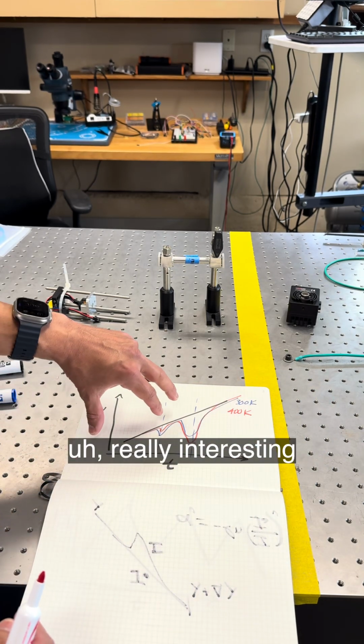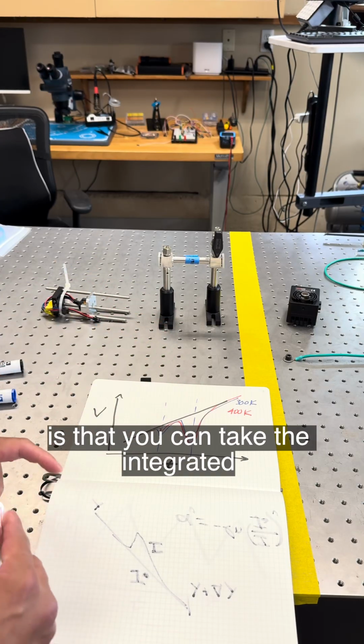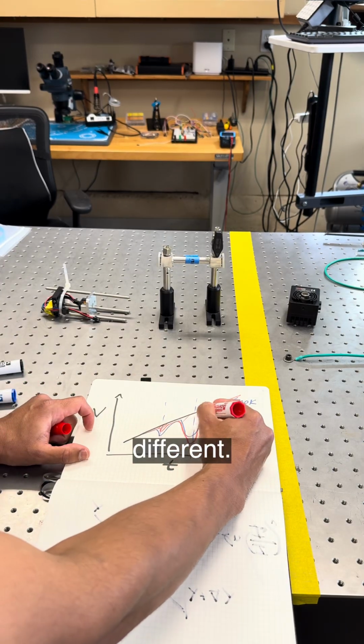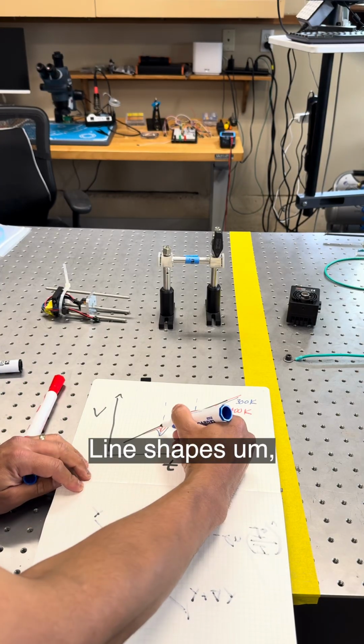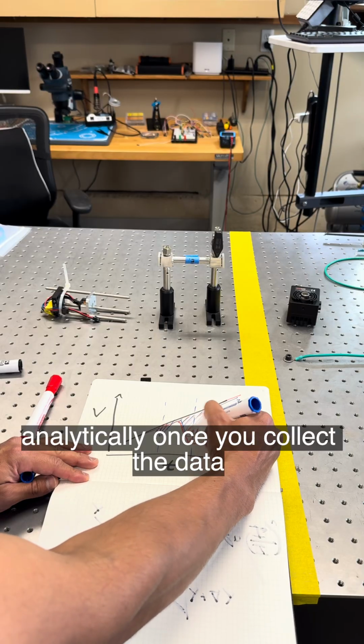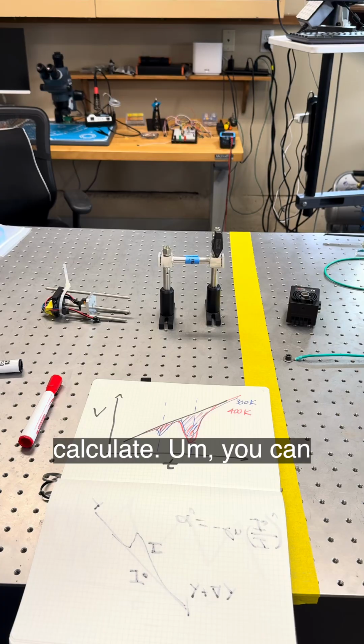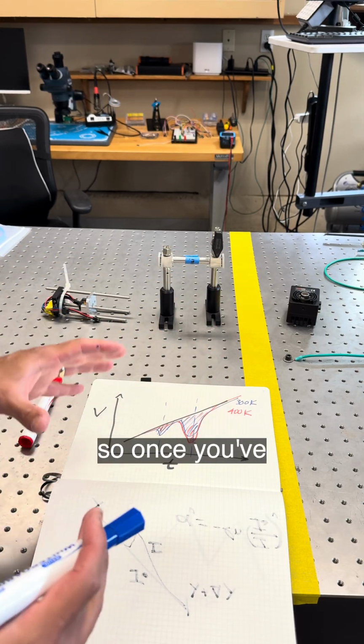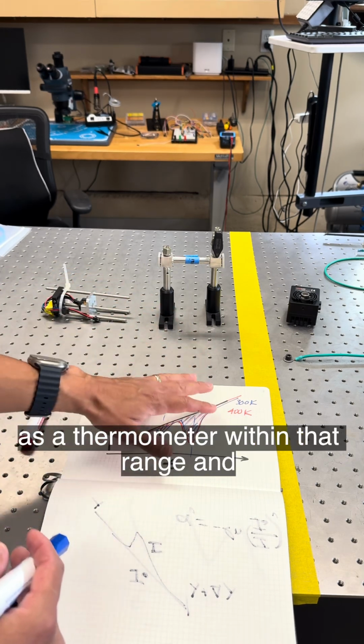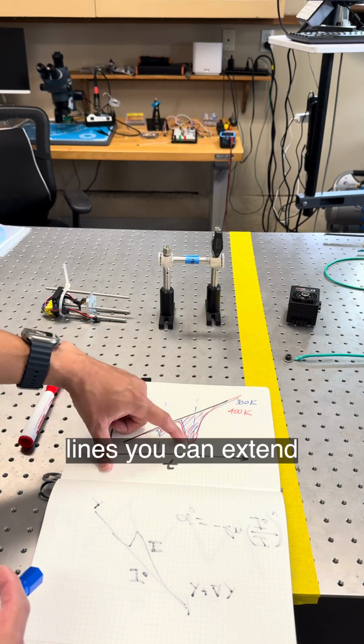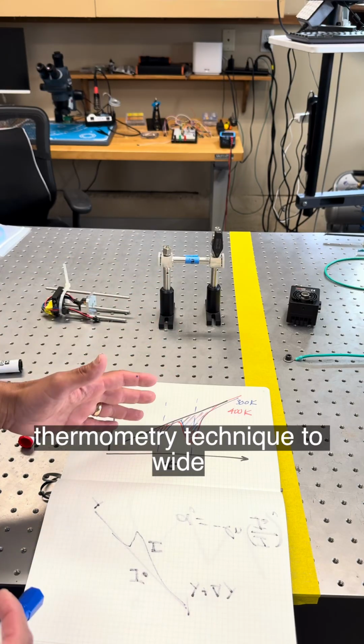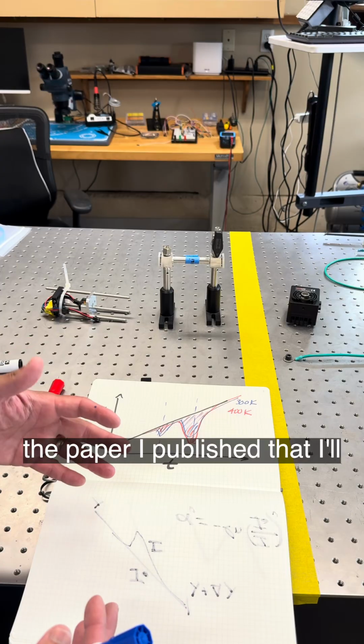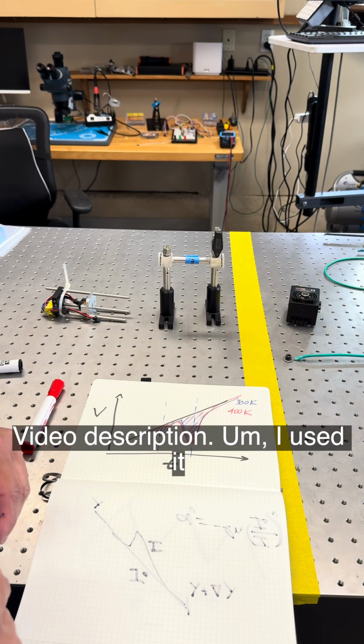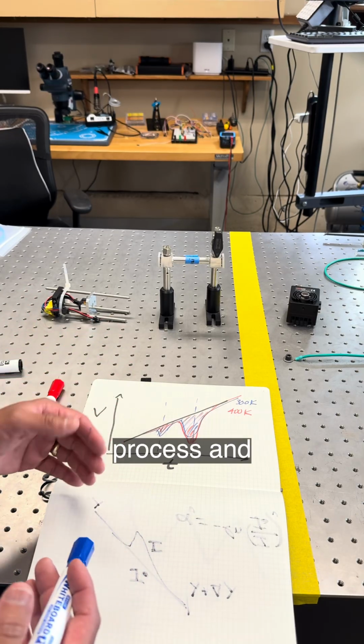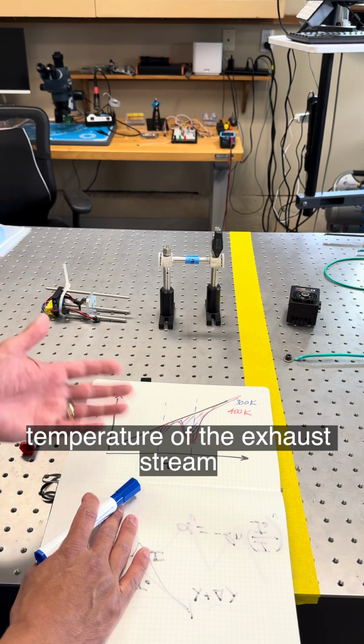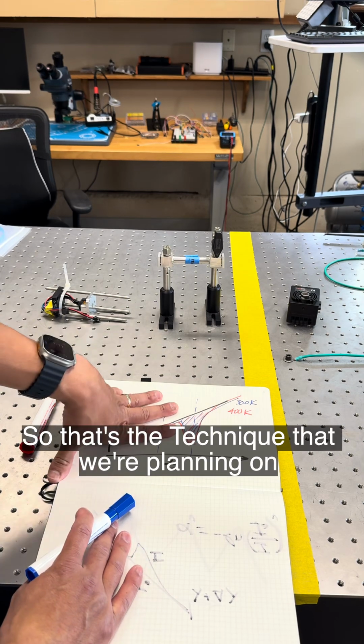What's really interesting and helpful from a thermometry standpoint is that you can take the integrated area of these different line shapes, and you would do this analytically once you collect the data. You can take the ratios and actually calculate a temperature of 400 or 300K. Once you've convinced yourself of this, you can use this as a thermometer within that range. And depending on the peaks of these lines, you can extend the operation of this thermometry technique to wide ranges. In the paper I published, that I'll reference in the video description, I used it in a biomass gasification process and was able to measure the inline temperature of the exhaust stream of this biomass gasifier. So that's the technique that we're planning on using.